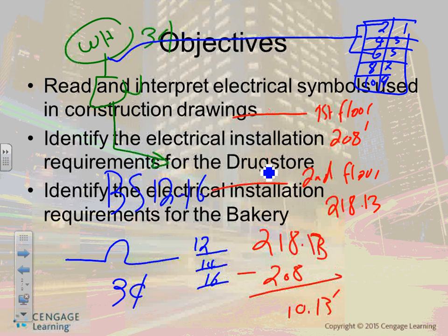Yeah. And we'll go over this also, guys, in detail. If you go to the upper right corner, please, service equipment. This is how they're going to do the service, guys. They're bringing a service panel. That's your service panel, upper right corner. It says service 3R enclosure, service 3R, rated for outdoor. The voltage 208, 120. They have the interrupting rating.